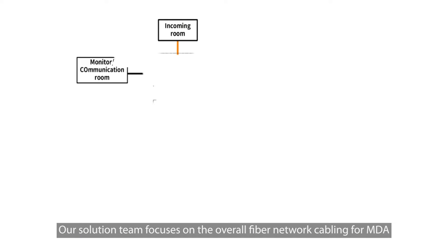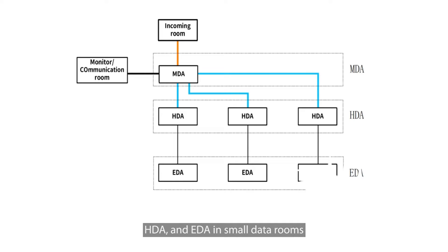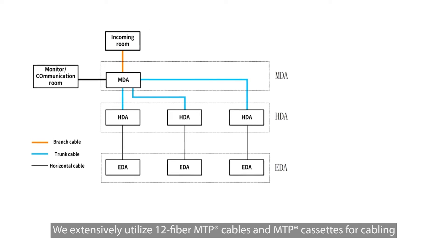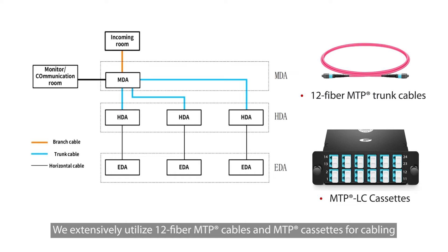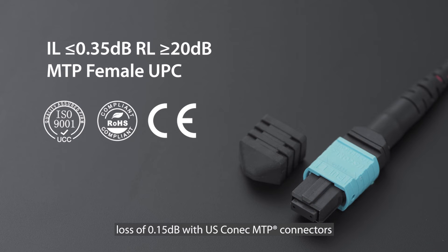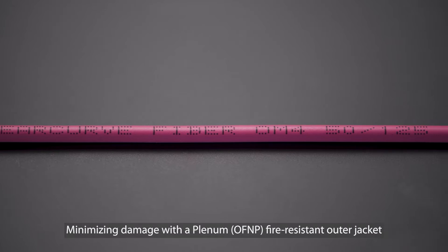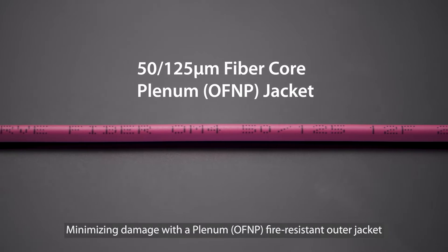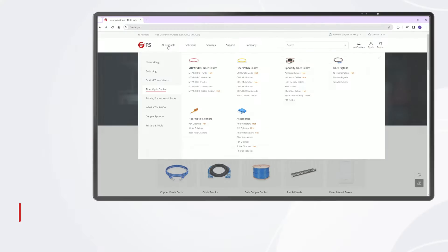Our solution team focuses on the overall fiber network cabling for MDA, HDA, and EDA in small data rooms. We extensively utilize 12-fiber MTP cables and MTP cassettes for cabling. The 12-core MTP cable achieves the lowest insertion loss of 0.15 dB with US Conec MTP connectors, minimizing damage with a plenum fire-resistant outer jacket, ideal for safe high-density cabling.